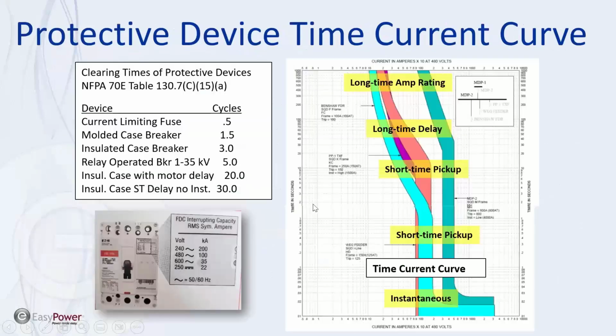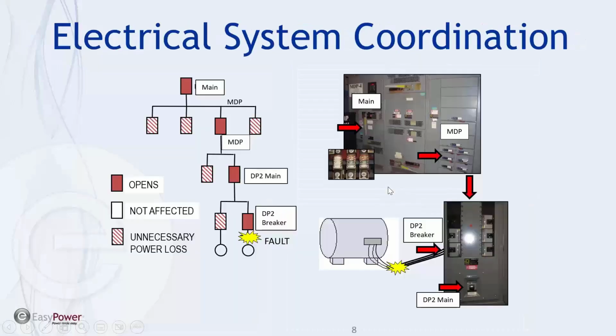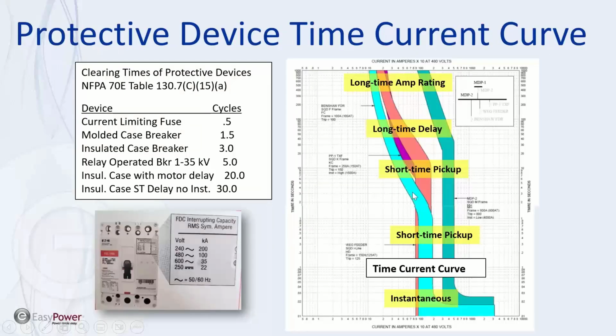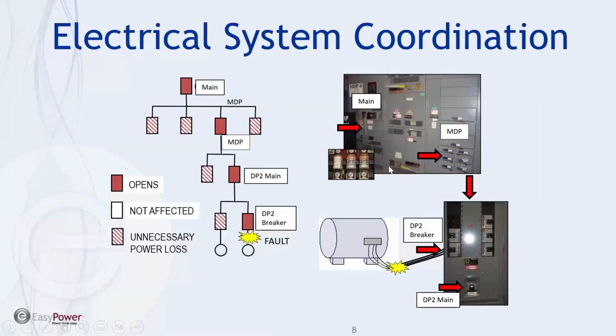So when I go back here, something like this is part of an arc flash study, which is a good benefit of doing an arc flash study, because you get a coordination and short circuit study at the same time. And there are usually time current curves in the study report. If an engineer sees this, he's going to drag this over to here with his mouse if it's adjustable. If it's not adjustable, he can't move it. Then he would make a recommendation to change the breaker to a different type or style with a different time current curve to make sure it's coordinated properly, and then you don't have the problems you would normally have in this case.